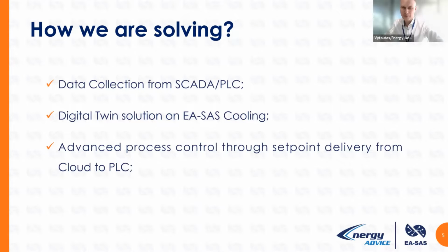So this is the maximum of what we must do. We should connect to your system and collect SCADA and PLC data, or only PLC data if it's a smaller system, because inside the SCADA and the controllers we have all the data required for a digital twin solution.